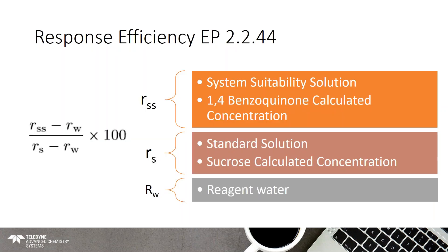Here is the formula given in EP 2.2.44. Basically, you take your system suitability solution — the difficult-to-oxidize 1,4-benzoquinone — subtract out your reagent water, then do the same with your sucrose solution: the calculated response of sucrose minus the calculated response of reagent water, then multiply by 100 to make it a percentage.